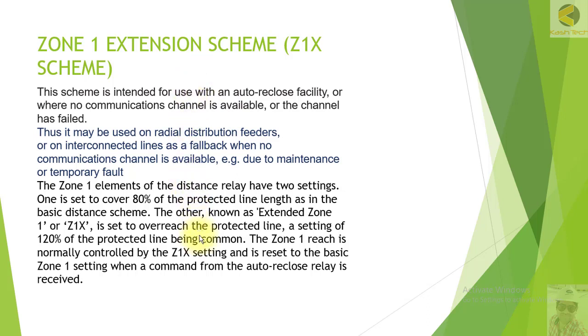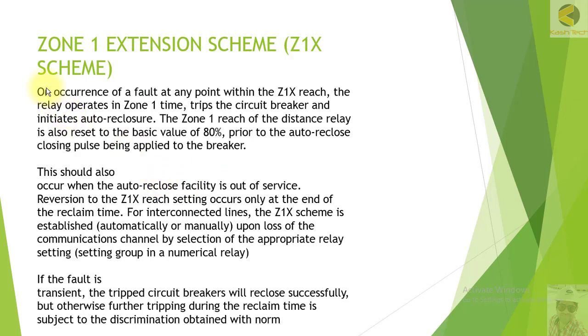Zone 1 is extended up to 120% in the first attempt. When the auto-reclose does reclosing, it is reset back to 80%. This scheme is useful where you don't have any communication scheme available but still want fast tripping. Fast tripping and system stability are the first priority here. This scheme is used on occurrence of a fault at any point within the Z1X reach.